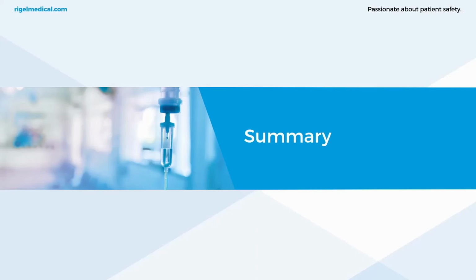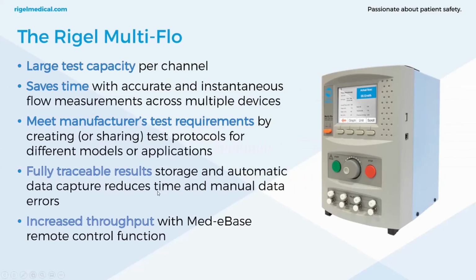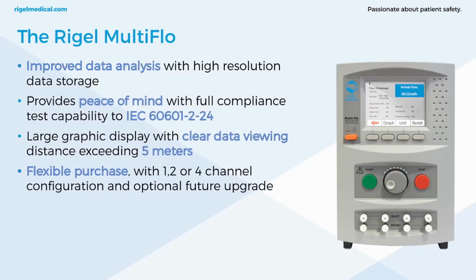So that brings us to the summary of this presentation. So a bit more of the key features. We understand there's a large test capacity per channel. It saves time with accurate instantaneous flow measurements across multiple devices. We know that it meets manufacturers' test requirements by creating or sharing test protocols for different models or applications. Got fully traceable results, storage and automatic data capture, and this reduces the time and manual data errors. And then also seen today the increased throughput with Med-eBase with its remote control function. Also got the improved data analysis with high resolution storage.